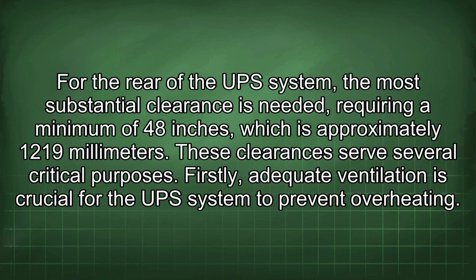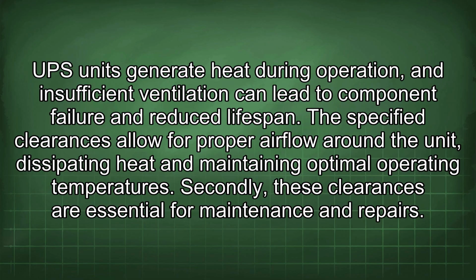These clearances serve several critical purposes. Firstly, adequate ventilation is crucial for the UPS system to prevent overheating. UPS units generate heat during operation, and insufficient ventilation can lead to component failure and reduced lifespan. The specified clearances allow for proper airflow around the unit, dissipating heat and maintaining optimal operating temperatures.